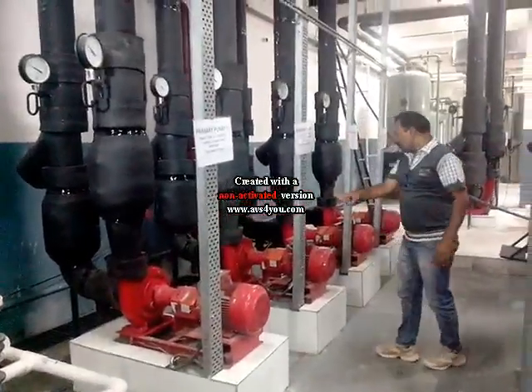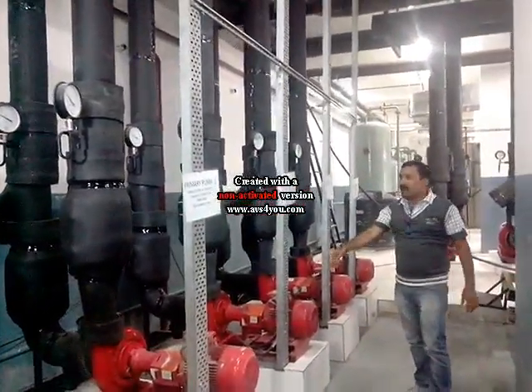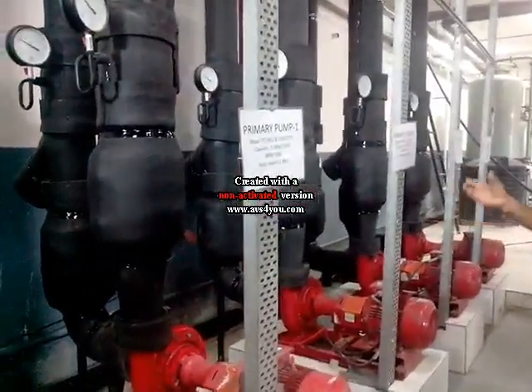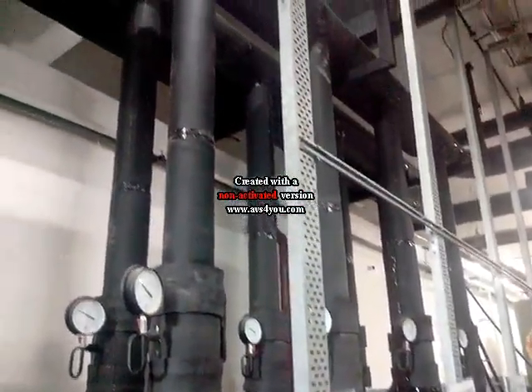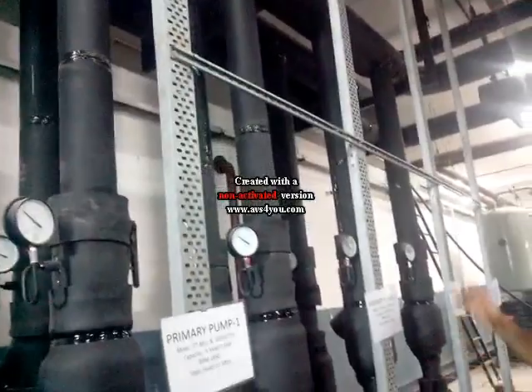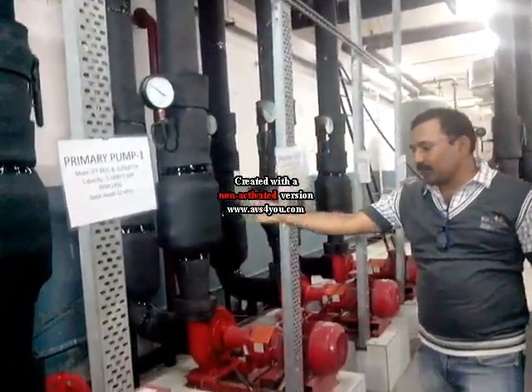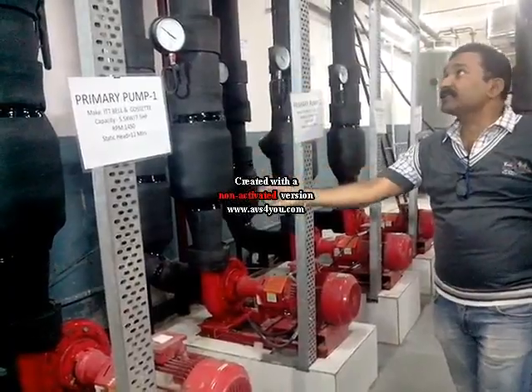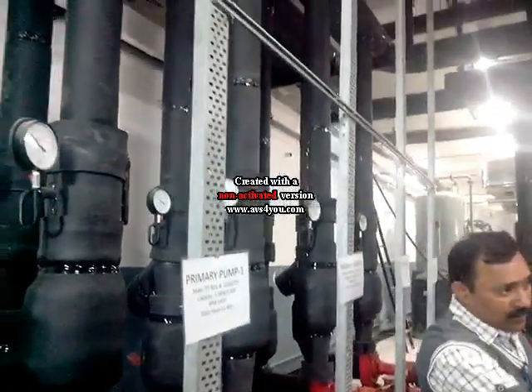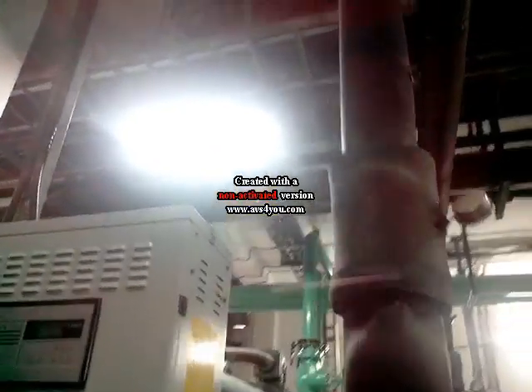These are 4 number primary pumps 1, 2, 3, 4. These pumps take suction from all AC units and feed to evaporator. Return water coming from these lines is a little warmer water. This water is fed to the chiller. From the chiller evaporator, chilled water is supplied to all AC units through secondary pumps.